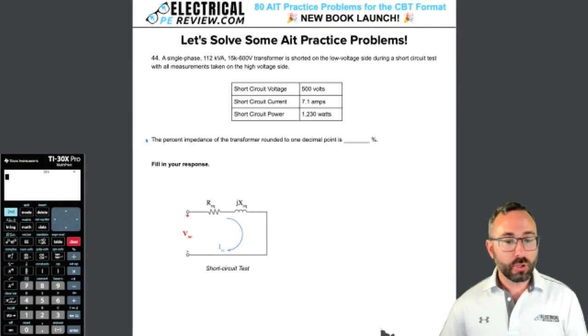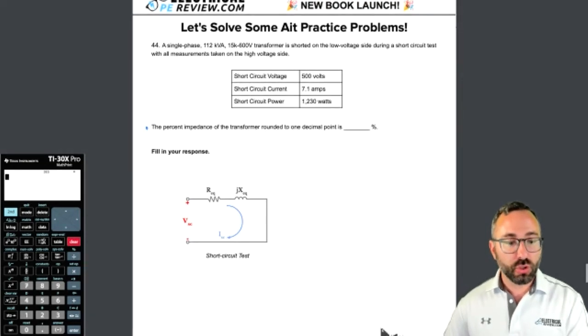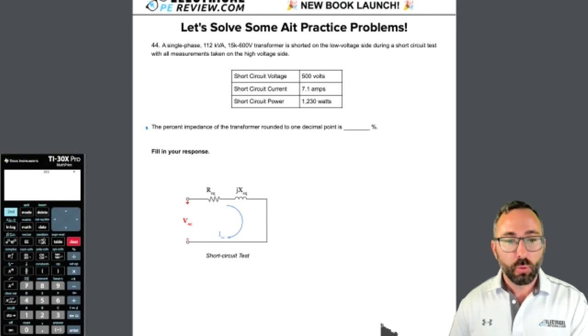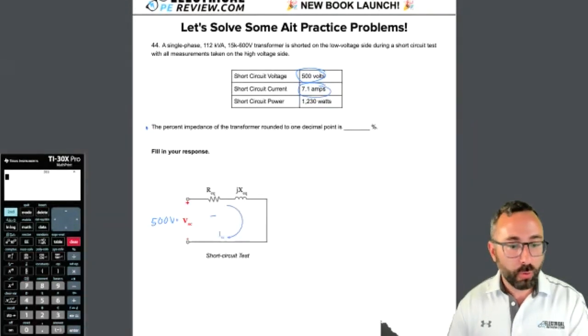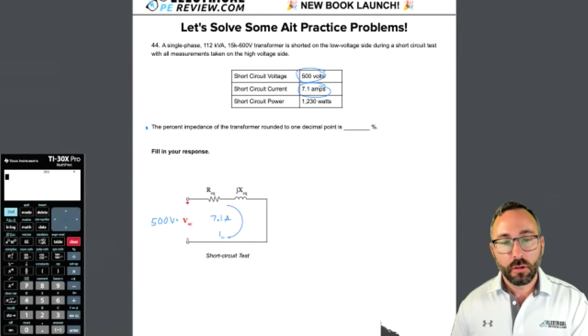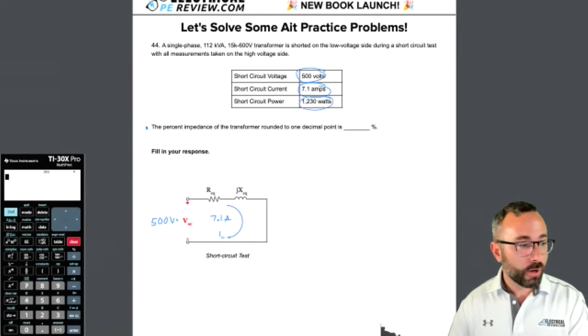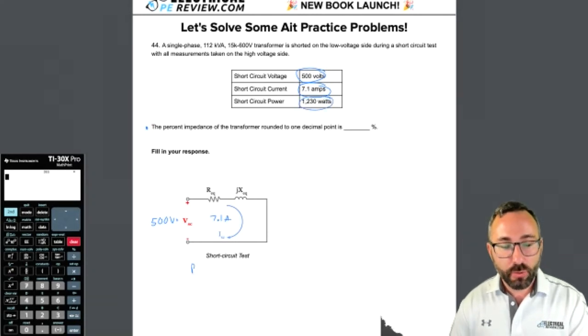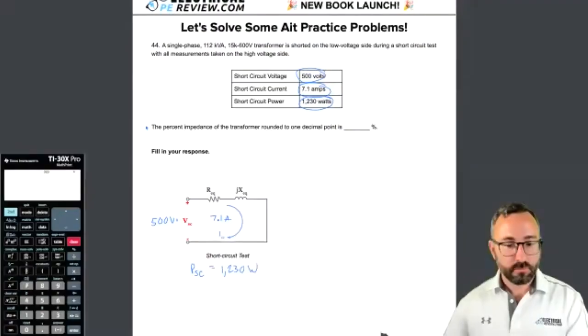First thing I'm going to do is fill in the short circuit test for the transformer. What's the short circuit voltage in the table? 500 volts. Next, what's the short circuit current that was measured? 7.1 amps. And last, what was the short circuit power? I don't know if I need this yet or not. I'm going to write it down anyway. P short circuit equals 1,230.